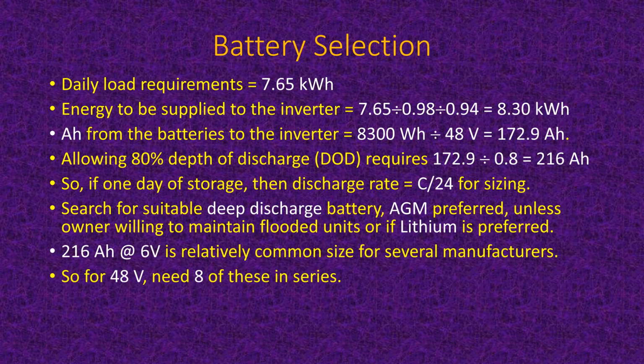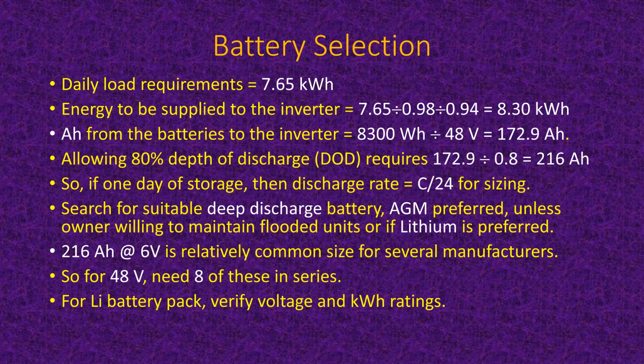Okay, so with lithium battery packs, you just verify the voltage and the kilowatt hour ratings. The ratings are typically somewhere in the neighborhood of 2 to 3 per element, but then you stick 6 of these 3 kilowatt hour things into a single package, and you've got an 18 kilowatt hour battery pack of DC.